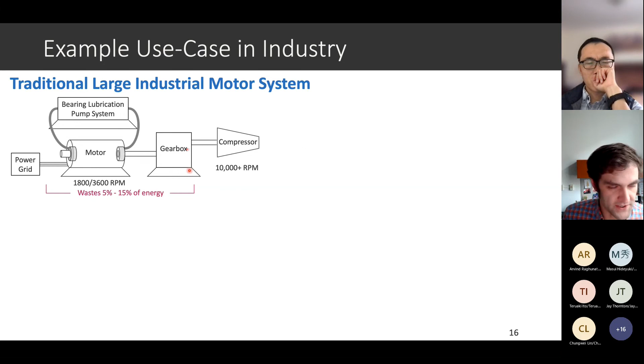The point of control for this kind of system, if you want different amounts of power out, is throttles in the path of the fluid the compressor is compressing. According to the Department of Energy, in these systems upwards of 80% of the power is dissipated in those throttles. So we draw all this power from the grid and then dump most of it in throttles. The reason is you have to size the motor for the maximum power you'd ever want to draw, then throttle it down for nominal cases so you can open up and get more power when needed. So that's a classical motor system.